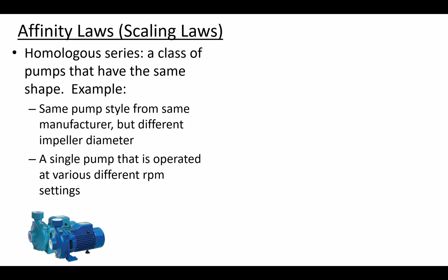System curve equals pump curve, and you solve for the flow rate and determine the operating point. But you can have a different pump curve if you take one of these pumps and change something about it. The calculations we're going to do today rely on relationships that explain this, which you can think of as before or after.